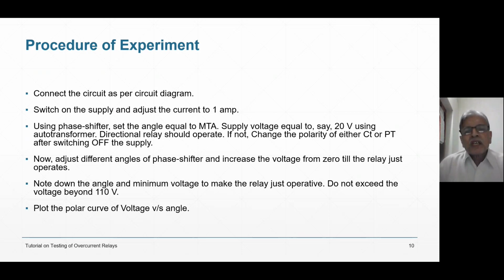Relay manufacturer will give. If he says that my MTA is 60 degree, adjust 60 degree. If he says that it is 90 degree, adjust 90 degree. Adjust by phase shifter 90 degree. On phase shifter, degrees are mentioned. You give supply voltage, say equal to 20 volt. 20 volt is more than enough because at MTA usually you require 1% of 110 volt. 1.1 is enough, but I am supplying 20 volts using auto transformer.